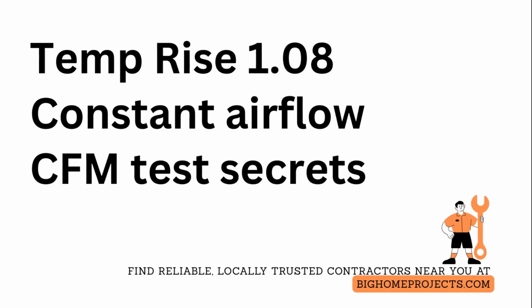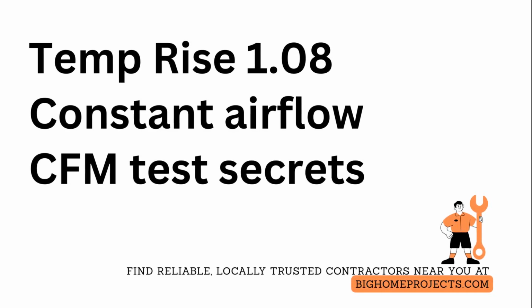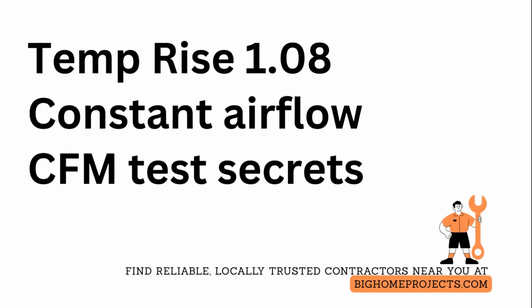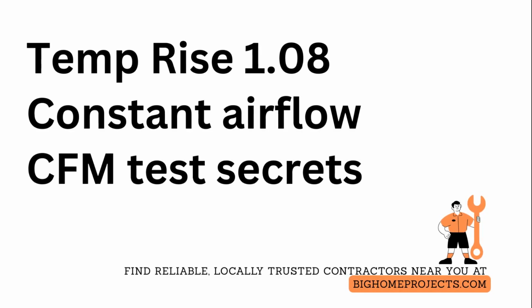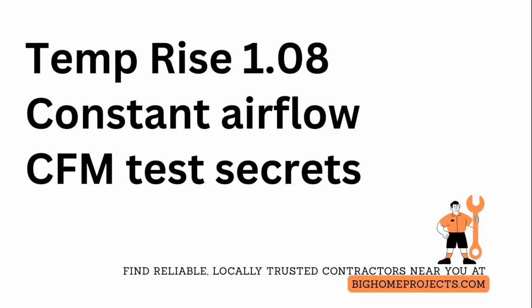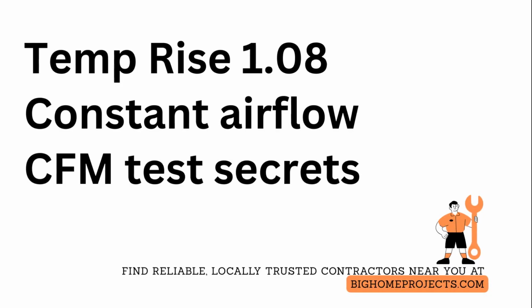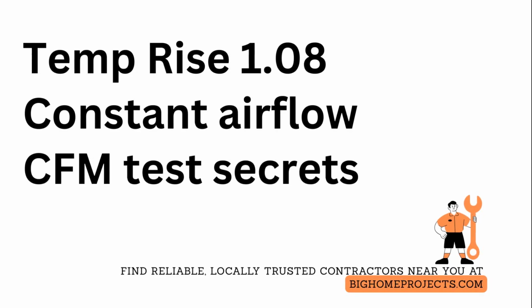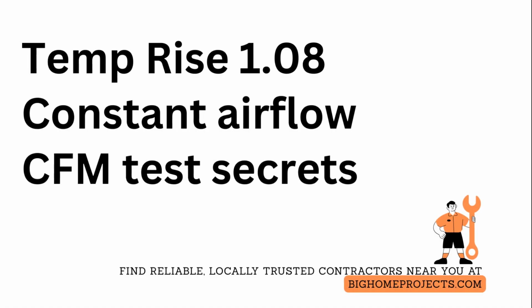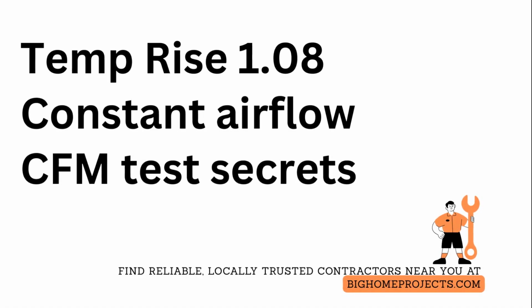Measure airflow cubic feet per minute with the heating, ventilation, and air conditioning temperature rise formula like a pro. Use the furnace nameplate input and output, steady-state temperature rise across the heat exchanger, and electrical readings to calculate cubic feet per minute accurately without fancy tools.